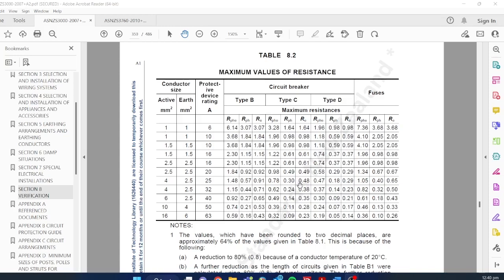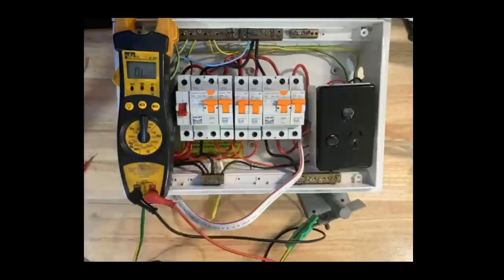So it's not as important for me to have the same low resistance on a 10 amp circuit breaker as I would have on a 20 amp circuit breaker, because I don't need as much fault current to trip it. So it's entirely dependent on that. Now, it's not super important for us to understand the ins and outs of that. What is important is to be able to find the right thing on our table. So if we look down the side there, it tells us the size of our conductors, and the one that we were using, just so you know, is 2.5 millimeter.